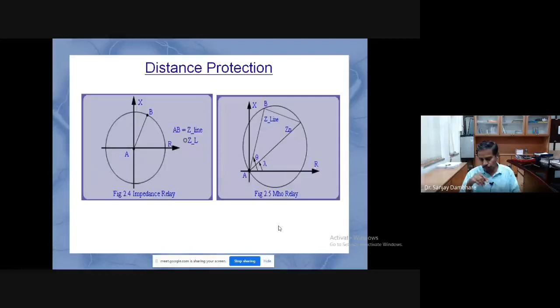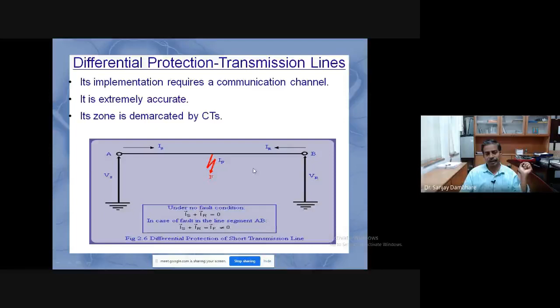The second philosophy is differential protection, which basically works on the difference between the currents. Current differential is more popularly used, but of course differential protection is there on the voltages, and then the power differential. Okay, so when it goes to the transmission line, you know that you cannot straight away compare this current. This current difference will not be zero, because there is a line charging current which comes from the distributed line parameters.